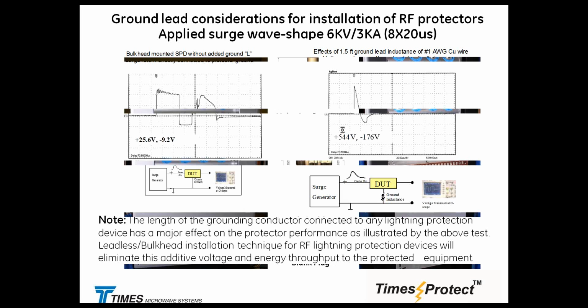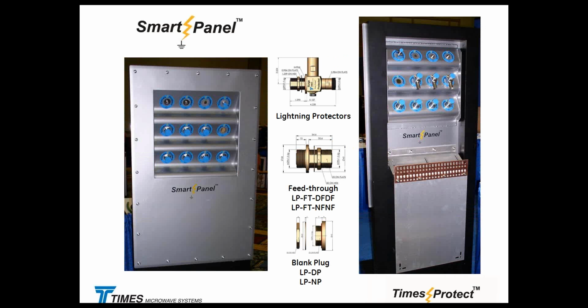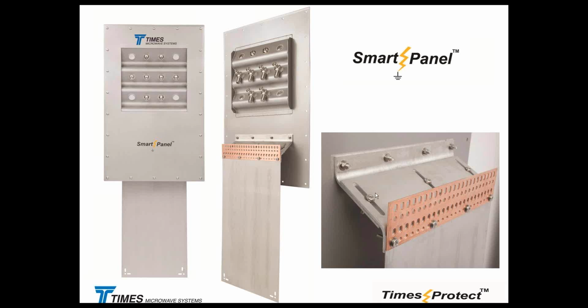So here is how that looks, basically loaded, and the optional accessories to it. Here is another marketing picture. You can adjust that plate to different wall thicknesses, anywhere from 4 to 8 inches, with a master ground bar for grounding all the rack equipment and everything that comes in. So we call this a single point by design, not by installation. Much less expensive way of doing business than going with all the components of the traditional method. And here is the area where we can cut out holes, put weather seals and bring any other services, and protect any other I/O ports and ground them right here to the panel or to this grounding bar.